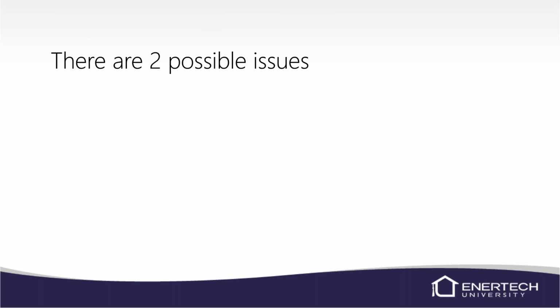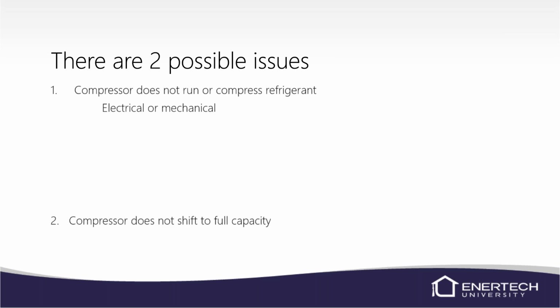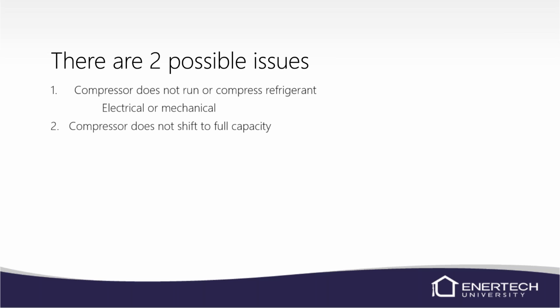Basically, there's two possible issues when a compressor fails. Either the compressor does not run or compress refrigerant. So that could be either electrical or something mechanically wrong inside the compressor itself. And you could also have a compressor that does not shift to full capacity. Easiest way to tell if it's not shifting to full capacity is amp draw. Sometimes you can hear it, sometimes you can't, just kind of depends. But we'll cover how to check that here in just a minute.